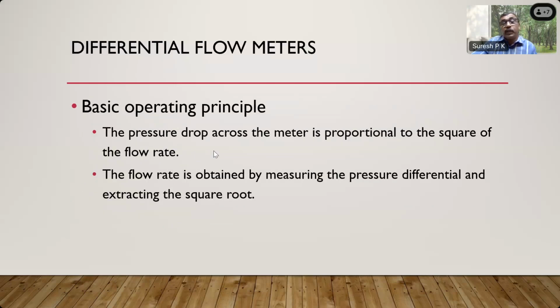In the differential pressure flow meters, the pressure drop across the flow meter is proportional to the square of the flow rate. Basically, an orifice plate is nothing but a plate with a hole. You make a hole in a plate, put it in place, and measure the differential pressure across the plate. You will get the indication of the flow rate. So very simple. The flow rate is obtained by measuring the pressure differential and extracting the square root, which is directly proportional.